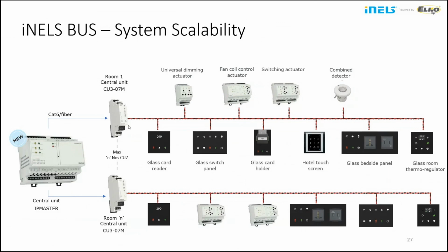One central unit is required even for very large installations, with no limit to connecting mini central units, since we use IP topology. The IP master connects to the mini CU using IP protocol at a commonly used Ethernet speed of 100 Mbps. The new IP infrastructure connects central units to the central iNELS cloud, allowing individual projects to be combined into functional units, used to combine multiple large-scale projects into centrally controlled projects. That's also a main application of this IP topology.